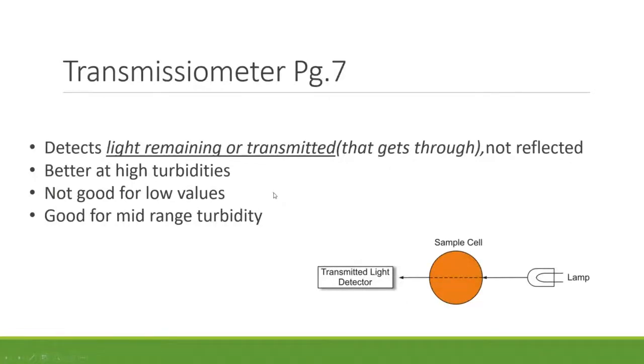The second type is the Transmissiometer, which detects the light remaining — the light that actually gets through rather than reflected. Unlike the other types that use reflective angles, this one measures transmitted light directly. These are better at high turbidities but not very good for low values, making them a good general mid-range device.